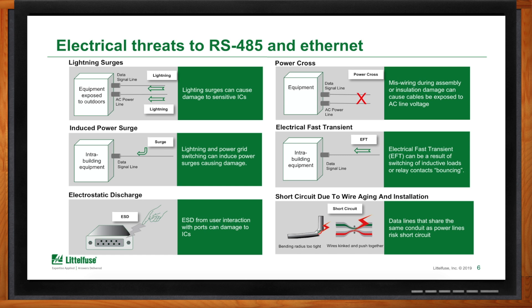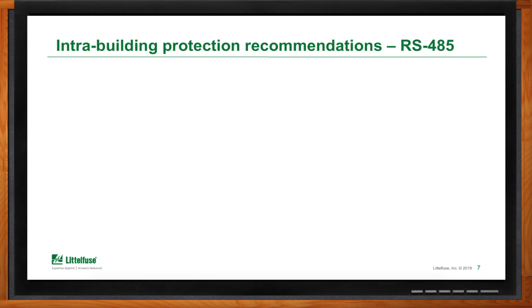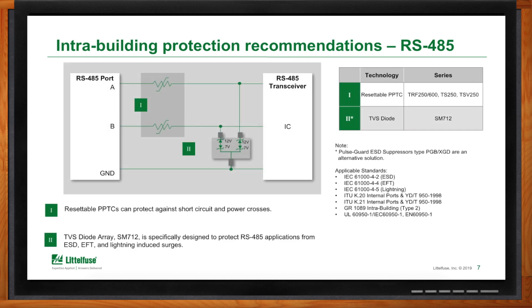For RS-485 intra-building protection, a resettable PPTC or PolySwitch — positive temperature coefficient — can protect against both short circuit and power crosses. For voltage, the TVS diode array SM712 is specifically designed for RS-485 and protects against electrostatic discharge, electrical fast transients, and some lightning-induced surges. As alternatives, you can use a Pulse Guard ESD suppressor type PGB or XGD. These all help you align to IEC, ITU, GR, and UL standards.